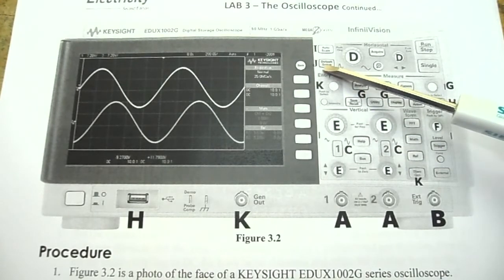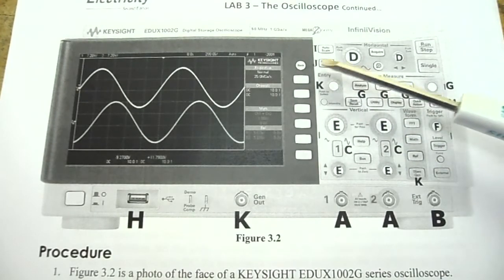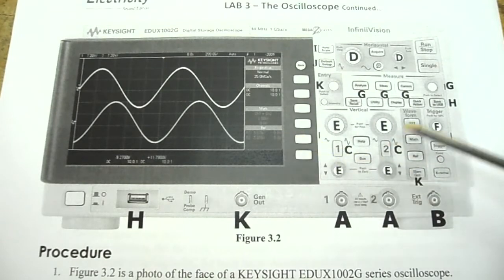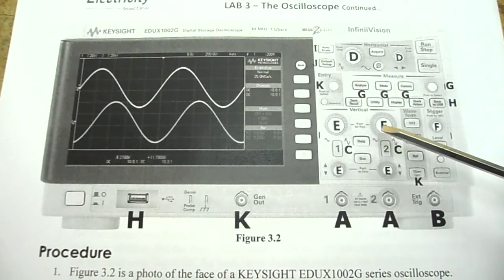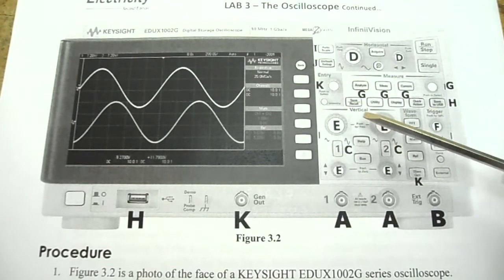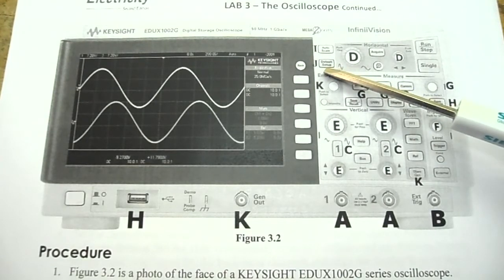J is the default setup. Now, because this oscilloscope has so many settings on it, you don't know what the last person did. So typically we go in, the first thing we do is a default factory setup on our oscilloscope so that we all start at the same starting point.